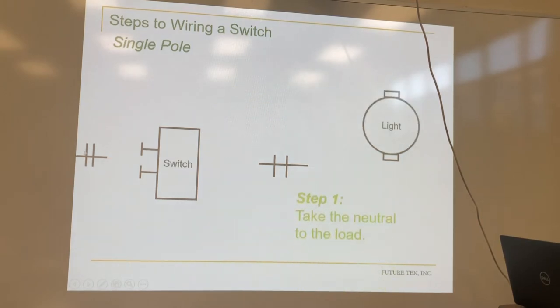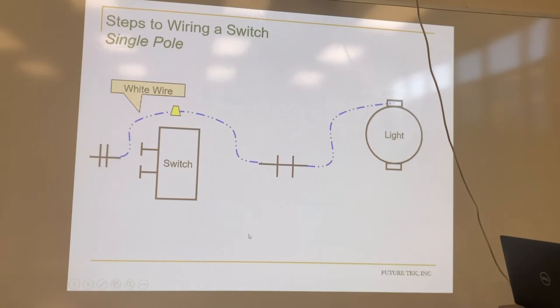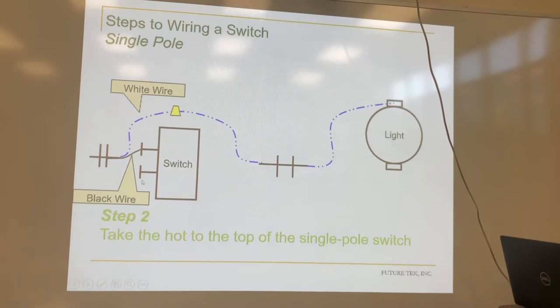Okay, so our 12-2 is coming in. What color wires are with 12-2? Black and white. So our white is coming in and it's just going to tie together in the box. Then it's going to go out and go straight to the load. The hot coming in is going to feed to one of the terminals on our switch. It does not matter which one because it's just a switch, just opening and closing.